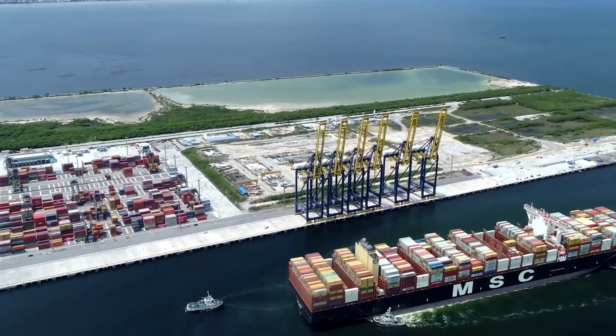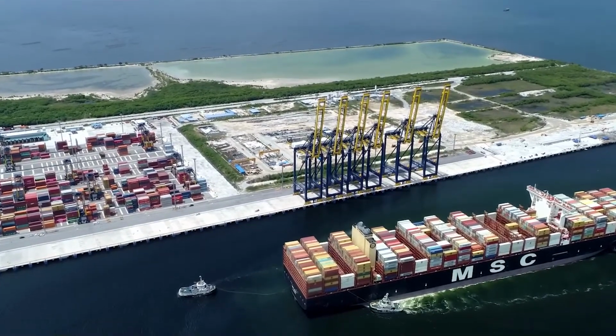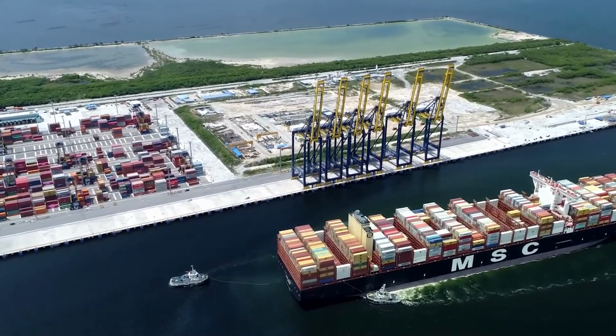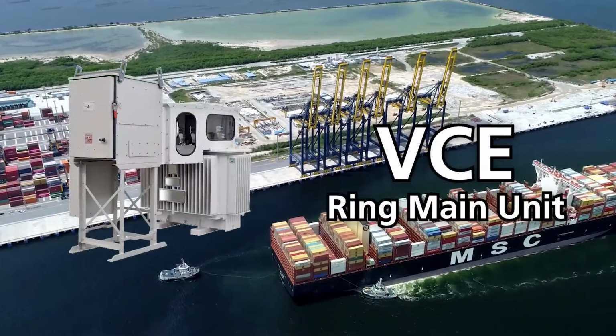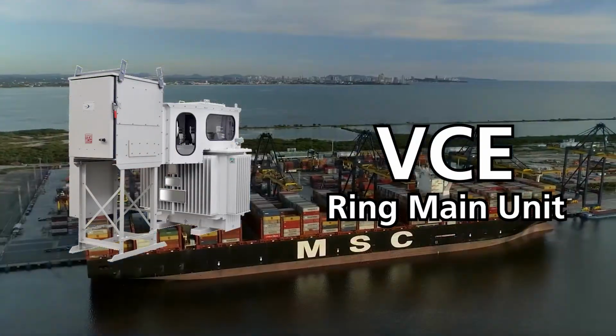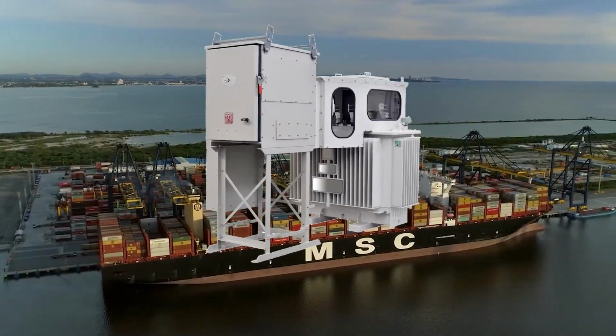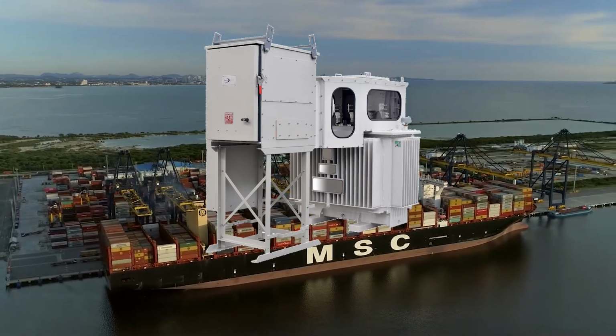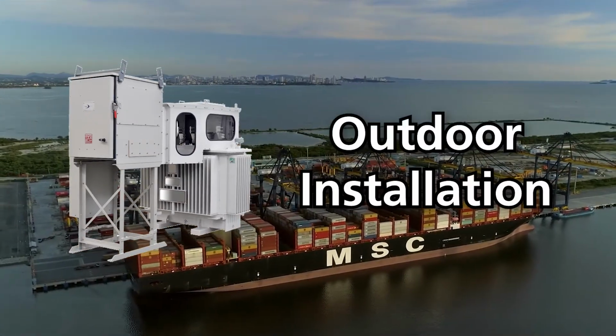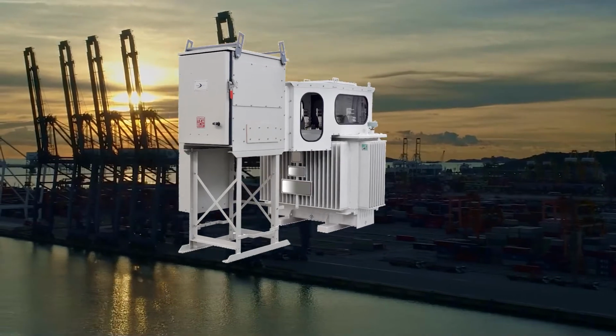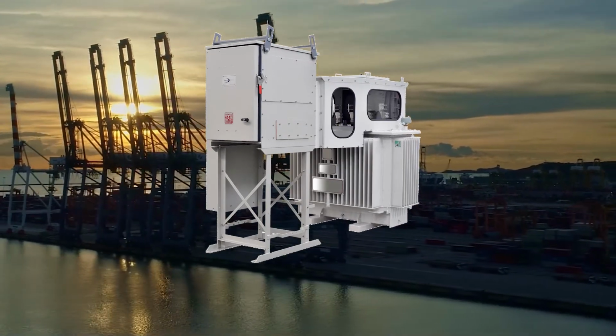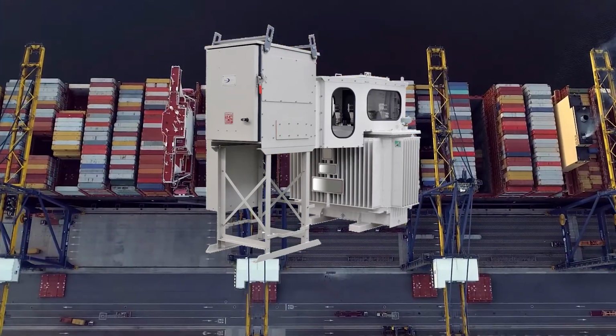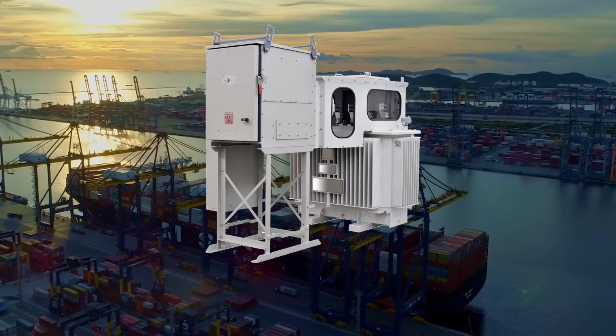In this clip, we will introduce another state-of-the-art model of Lucy Electric ring main unit, which is the VCE ring main unit. This ring main unit is designed to align with the IP54 standard to support outdoor installation. It applies a vacuum circuit breaker together with a relay to protect transformers.